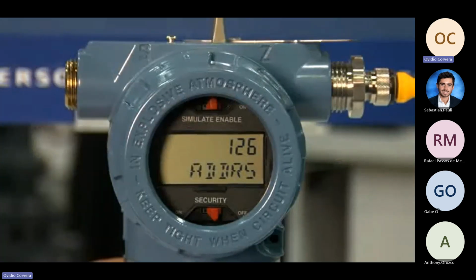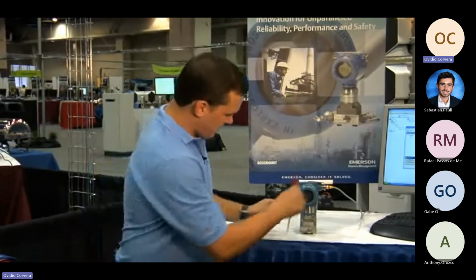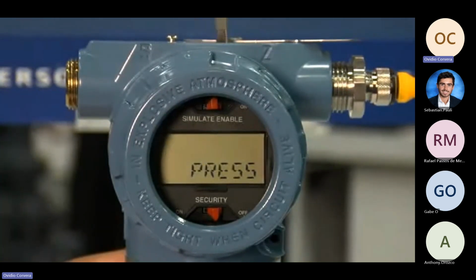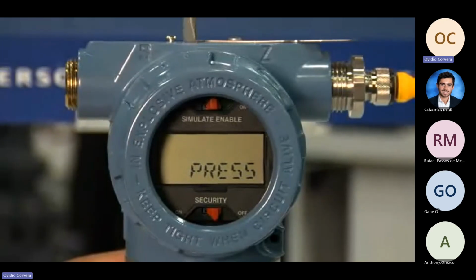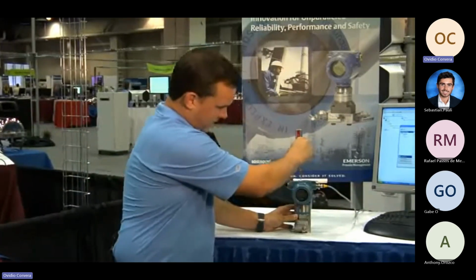Standard commissioning includes setting the address, configuring engineering units, and then eliminating any errors due to mounting pressure effects. The first step will be to set the address. Here we'll set the address to 36. You can see with the simple scroll and select operation, it's very easy and responsive to go through the configuration. Next, we'll configure engineering units for pressure, PSI. This new transmitter offers pressure, level, or flow output configuration. Last step, assuming we've mounted the transmitter onto the process, we'll zero out any errors from that mounting procedure.